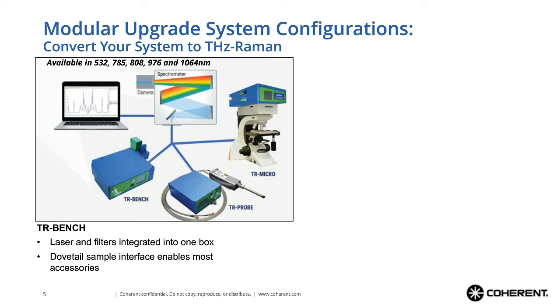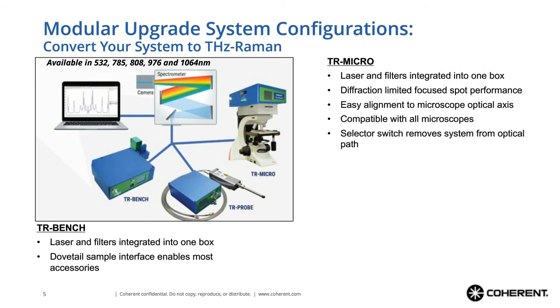The TR Bench integrates everything into a single box with a versatile dovetail flange for easy connect and disconnect to various sample interface accessories. The TR Micro adds more internal optics to align the beam to the optical axis of any standard microscope. All Raman signals are returned to the system, but shorter wavelengths are transmitted through to a CCD camera or eyepiece placed above the system. An integrated selector switch allows the optics to be removed from the beam path without interfering with any other instruments on the microscope.